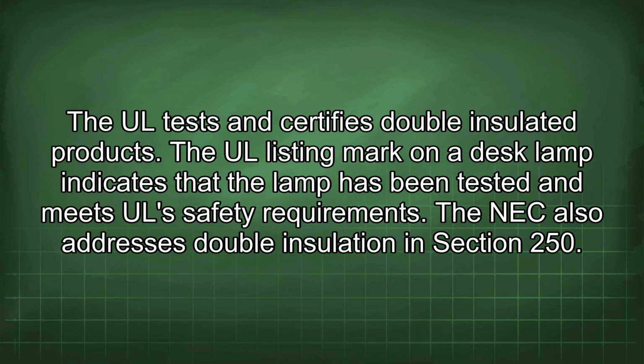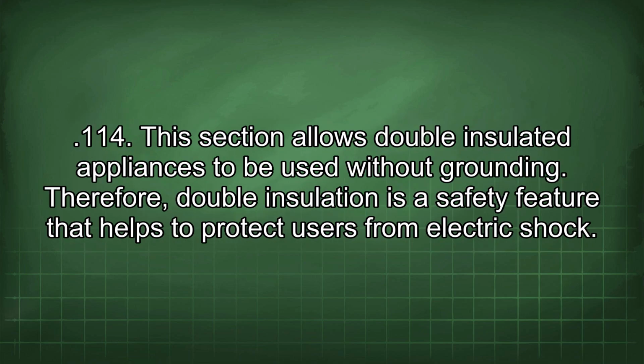The NEC also addresses double insulation in section 250.114. This section allows double insulated appliances to be used without grounding. Therefore, double insulation is a safety feature that helps to protect users from electric shock.